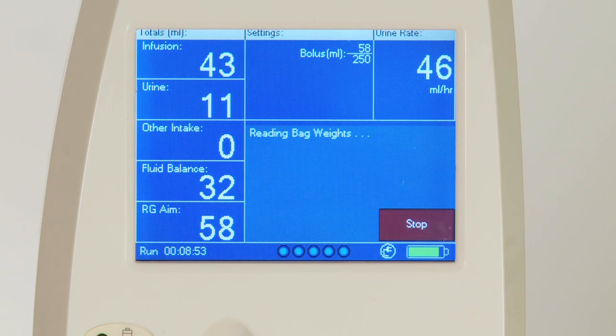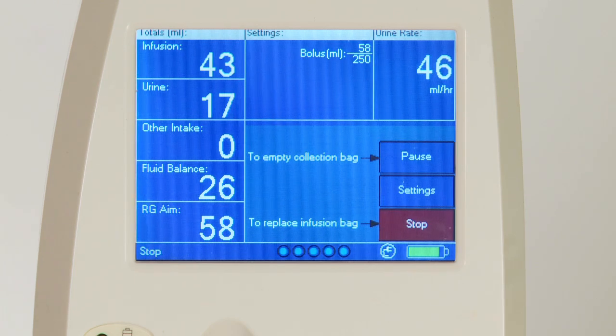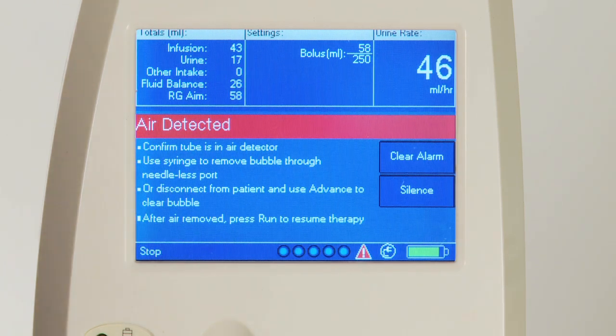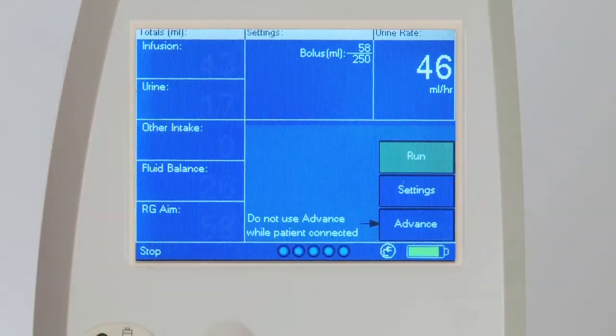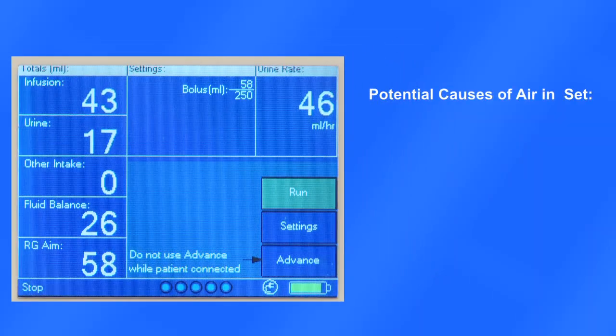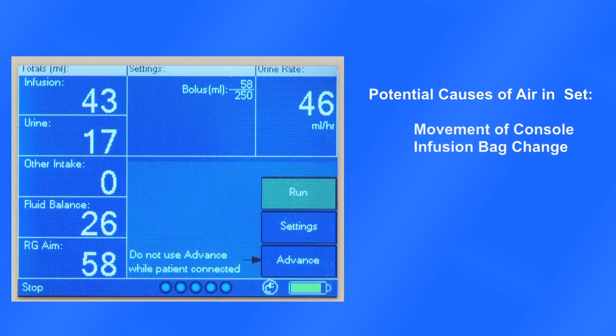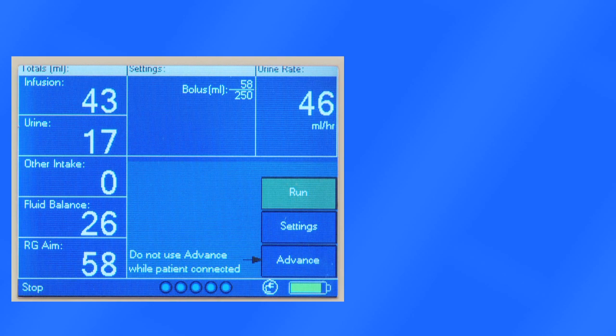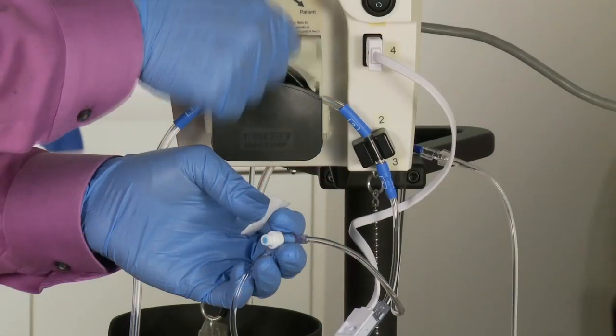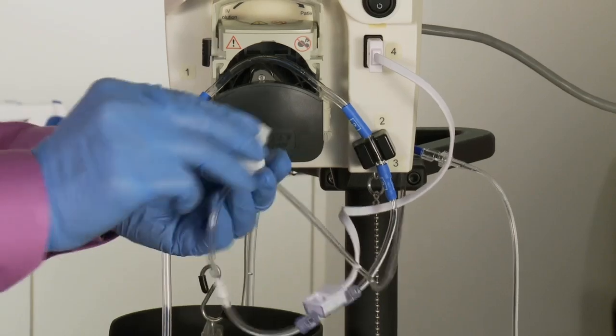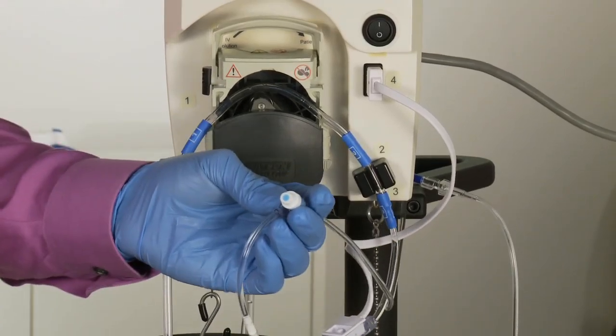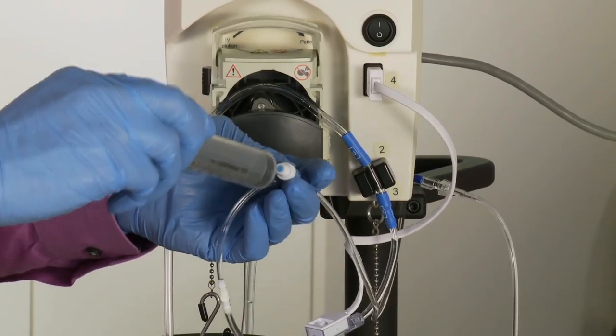Air detected: if the console detects air, the pump is stopped and the air detected alarm is displayed. Press the clear alarm button. Potential causes of air in the set are movement of the console, infusion bag change, or a crack in the set. There are two ways to purge the air. Disconnect the patient and use Advance to flush out the bubble, as demonstrated earlier. Or open the pump door and use a syringe to remove the air through the needleless port using good hygienic technique.